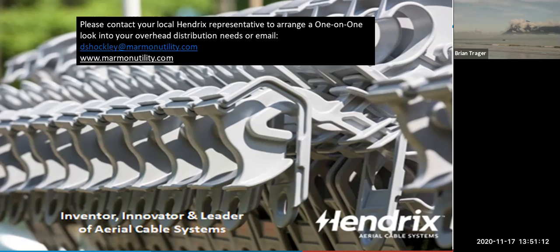If they can work up new work methods that allow faster, more reliable, safer work while working spacer cable, while still respecting National Electric Safety Code and their own utility standards, then that's fantastic. Otherwise, they have to maintain all of those distances. We're not saying you can take any shortcuts with spacer cable or tree wire.